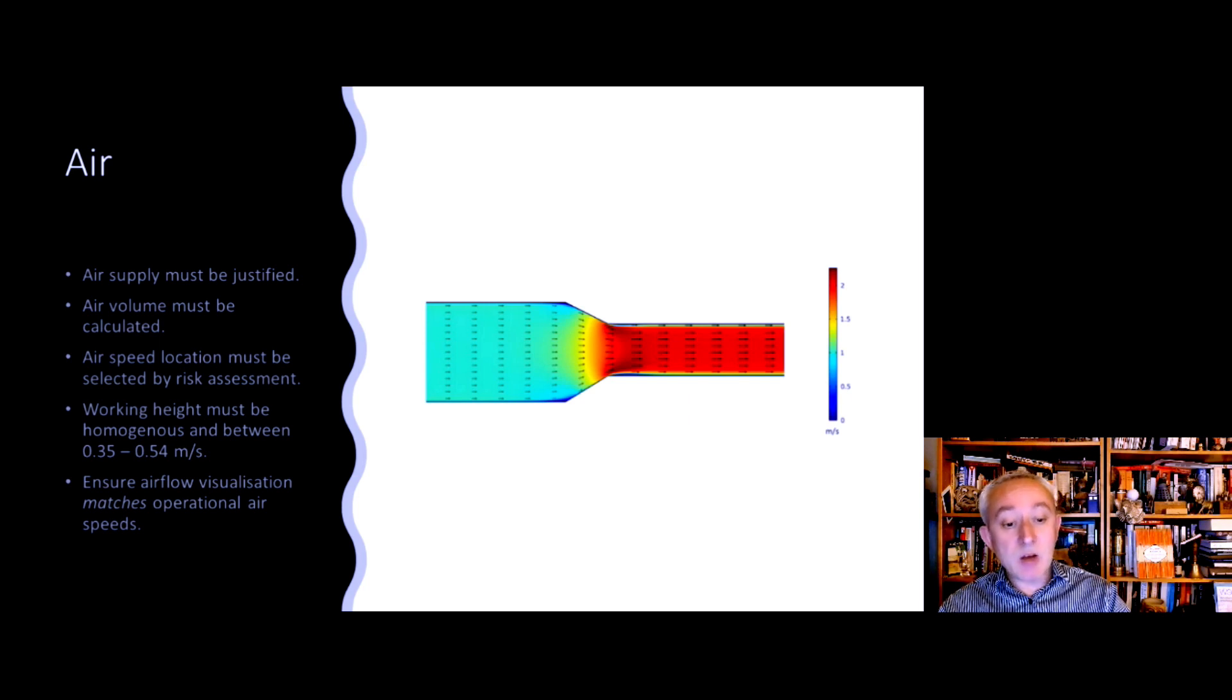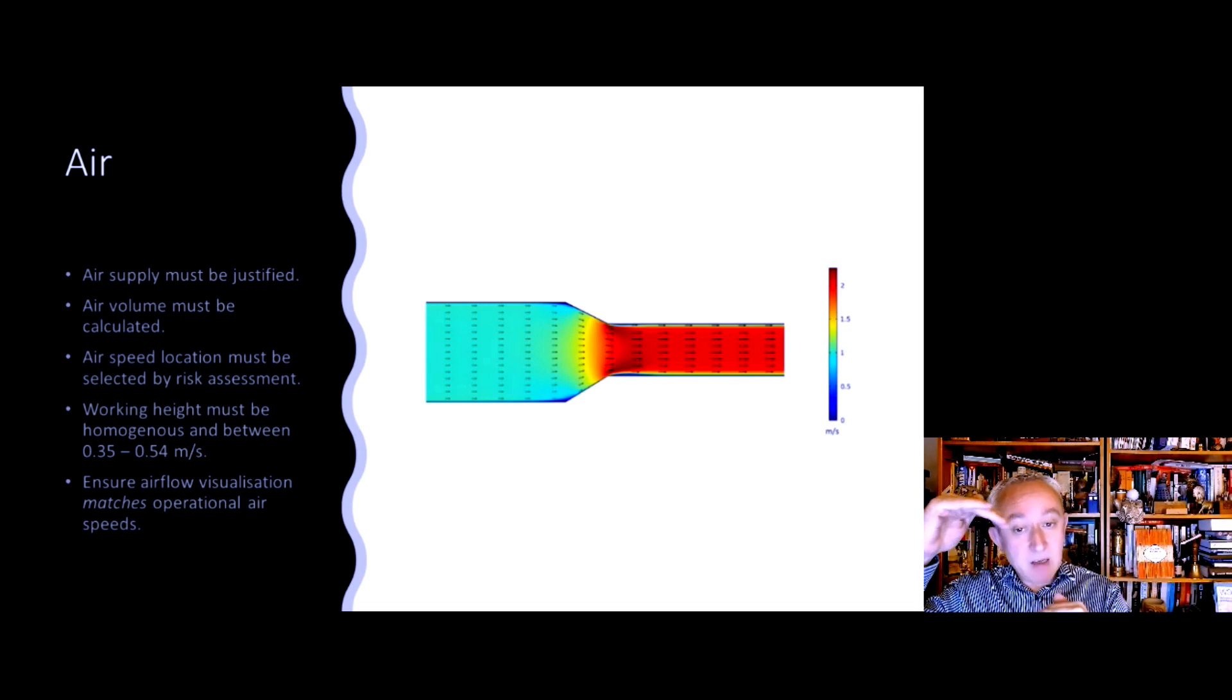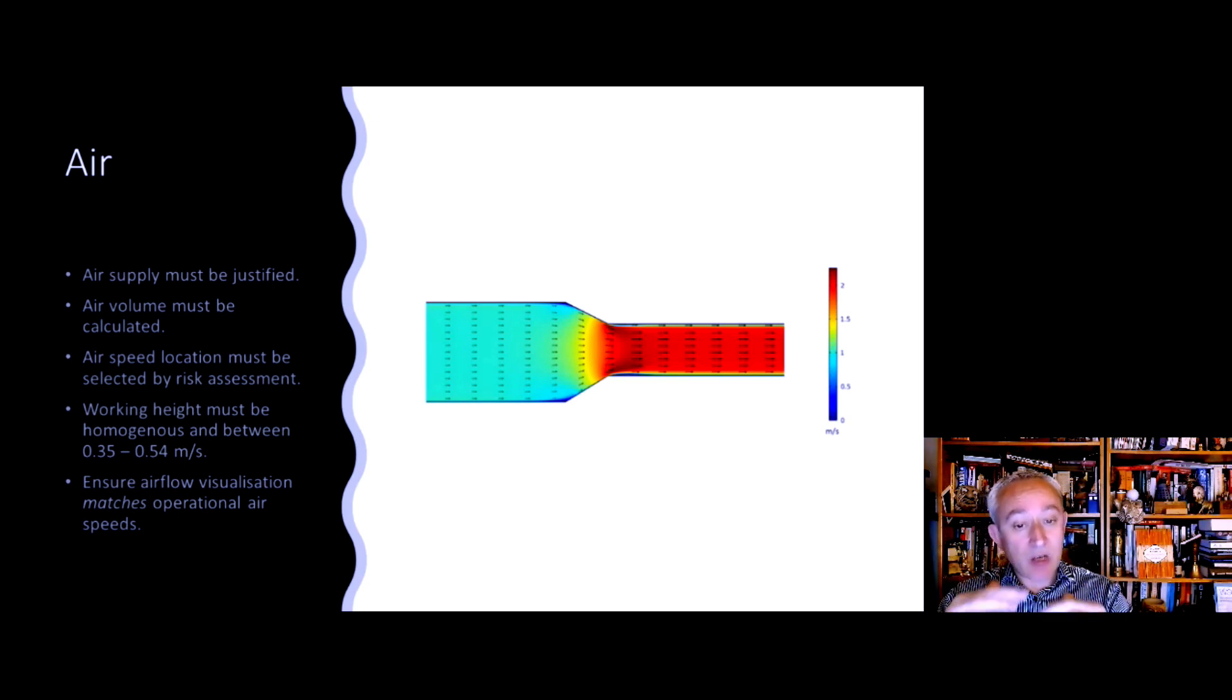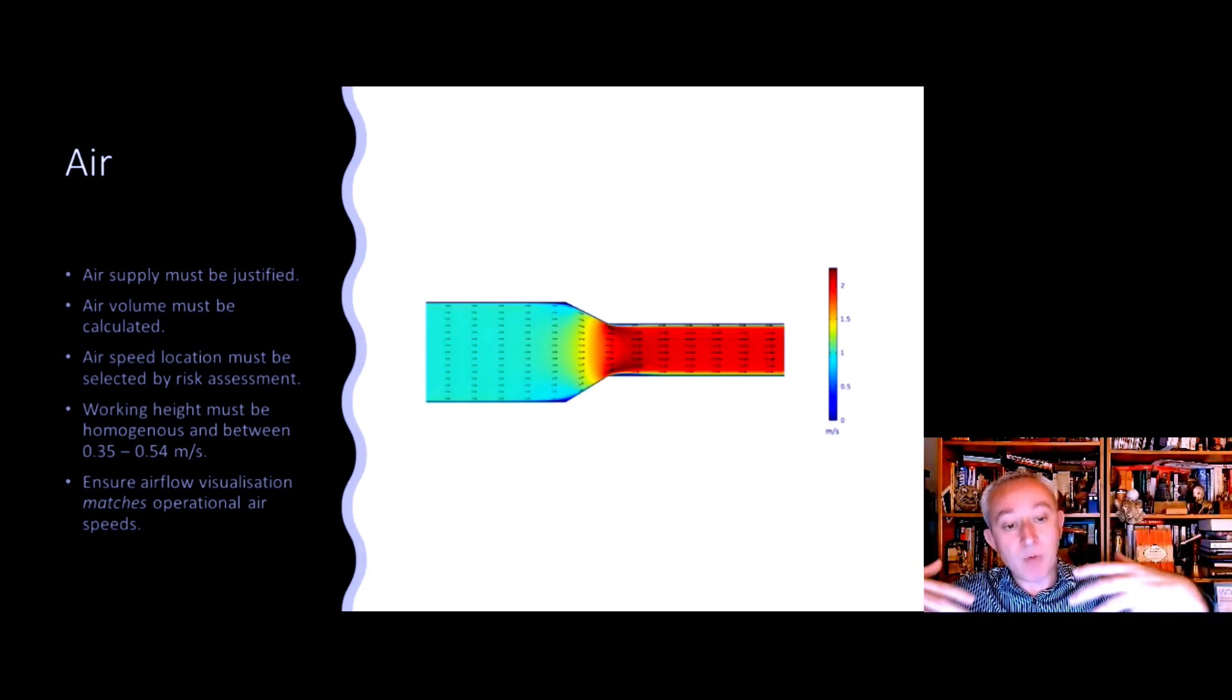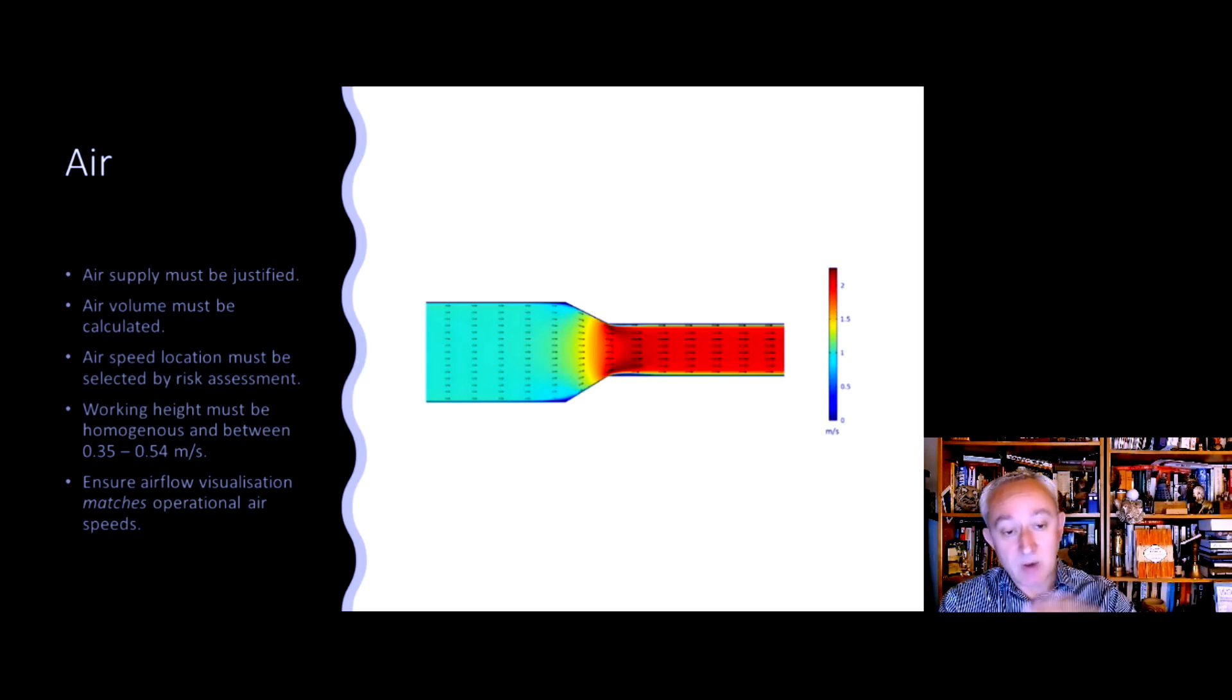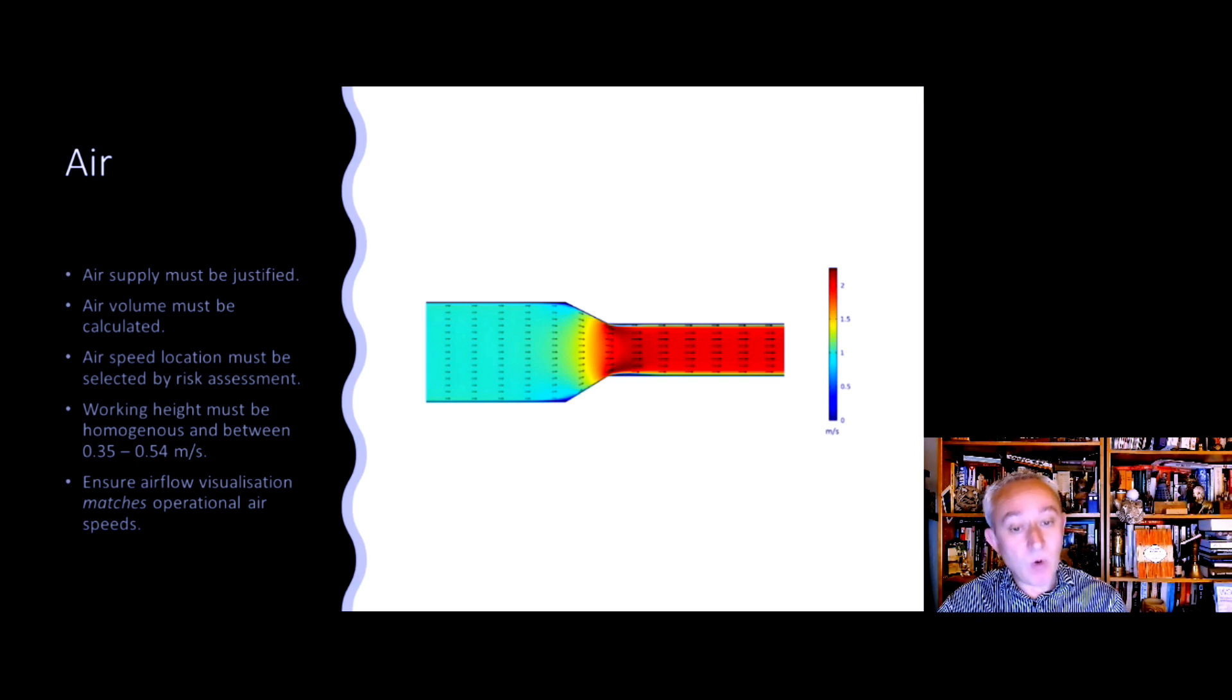Air is also important for the clean room classification process. For unidirectional airflow systems, the speed of the air supplied needs to be justified in any qualification protocol, and the location at which airspeed measurement for the incoming air is recorded needs to be justified. That airspeed coming in should be of an appropriate speed so that we can achieve appropriate unidirectional airflow movement and get appropriate protection of product and open components. Also, at working height, which is often defined as just above the height of an open vial, this is a homogeneous airflow and it is between 0.36 and 0.54 meters per second unless otherwise justified.